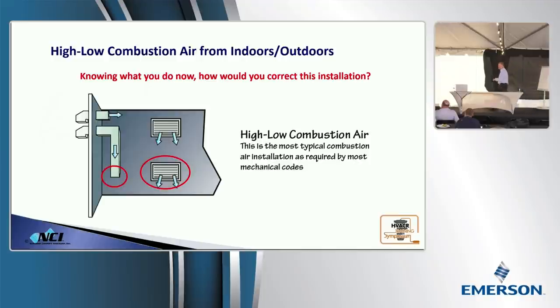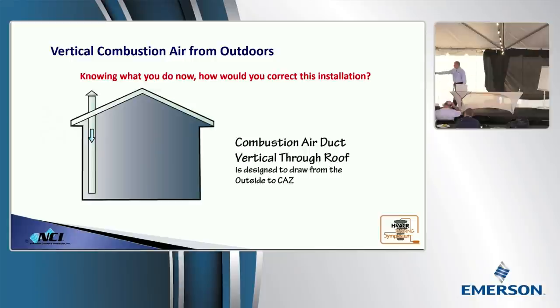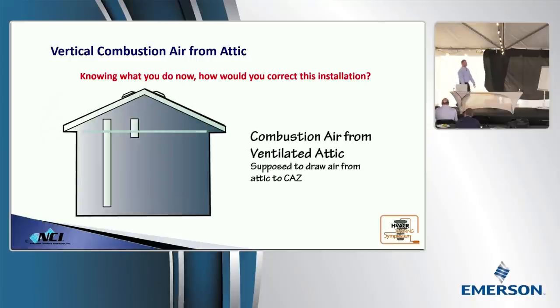You can do the same thing on this installation. If that's a 6-inch duct that's going through the ceiling, two 6-inch elbows back to back, and you will seal that off, and that will make a trap. You'll be amazed at how it'll change it, because then it has to overcome that cold column of air and that gooseneck of that trap. What about a high-low? If it's a high-low, two elbows back to back on the bottom, a 4-inch cap in the top one, because we're going to make the equipment safe. It shouldn't need a secondary flue. Don't give it a chance to leak.